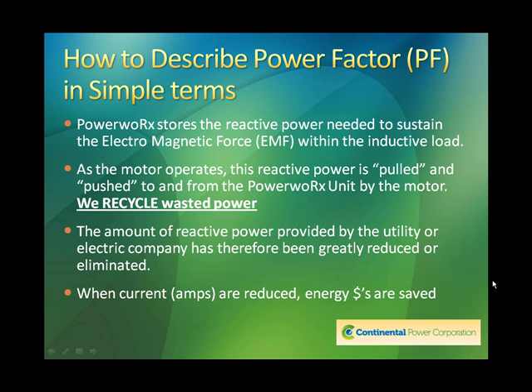The amount of reactive power provided by the utility or electric company has therefore been greatly reduced, or in some cases totally eliminated. And here is the key. When current, which is measured in amps, is reduced, energy dollars are saved. Now, there are going to be some electrical engineers, just like me, who say, wait a minute, I know when you improve power factor, you reduce power factor penalties, and that's where you get your savings. I know when I was at Purdue, we were taught that improving power factor does not save on kW or kilowatt hours. Well, it may not be a direct relationship, but indirectly it absolutely does, and we'll get into that here in a moment.